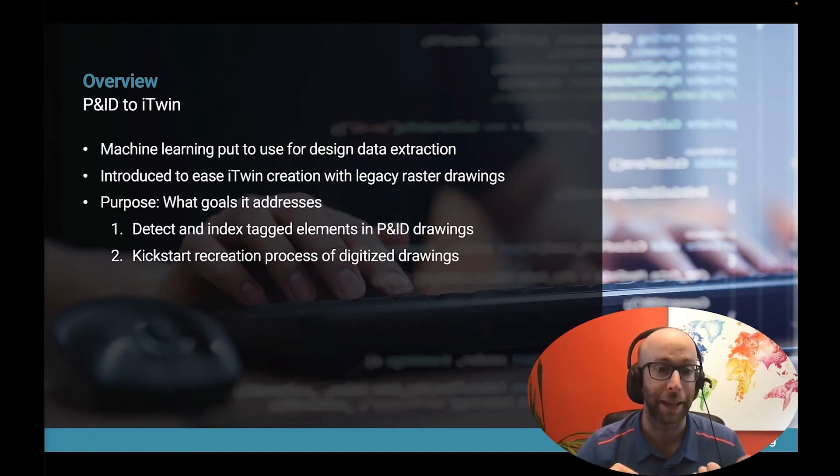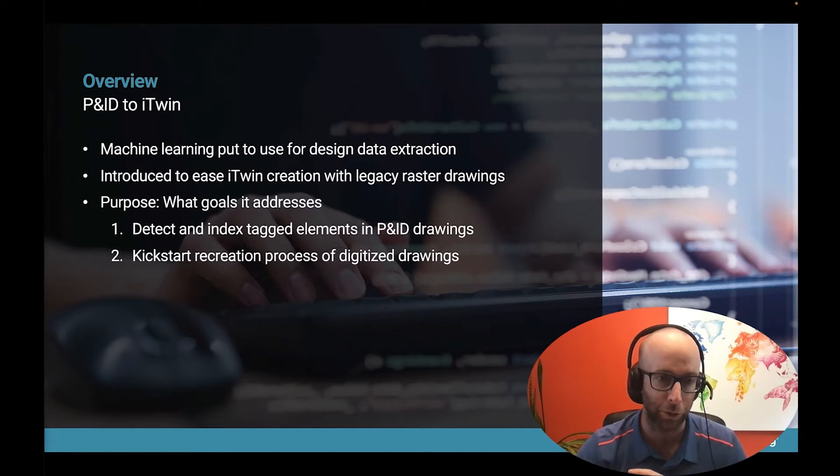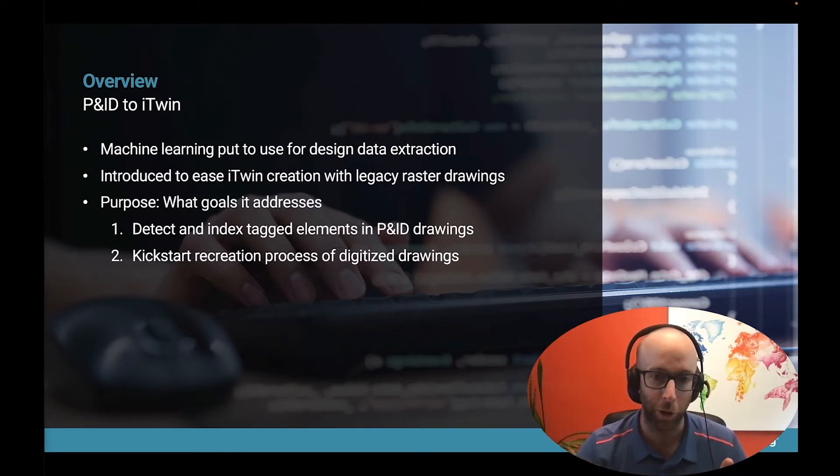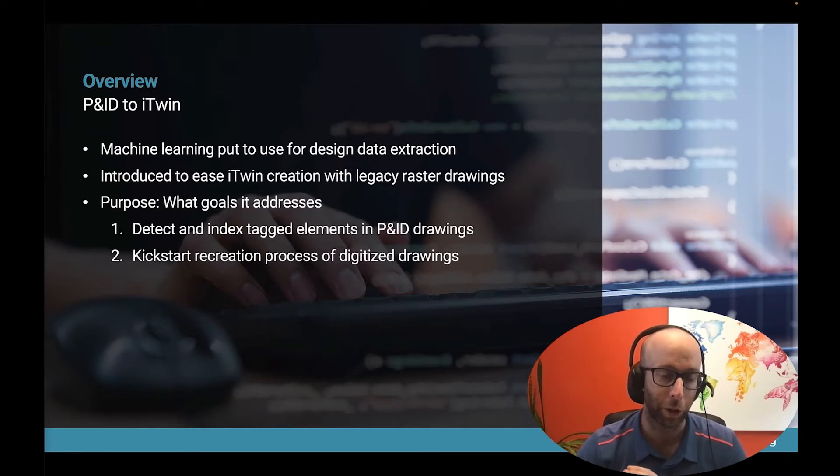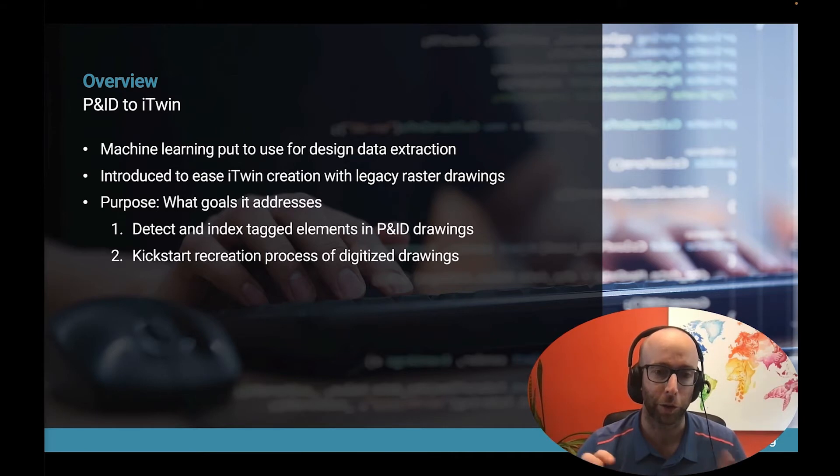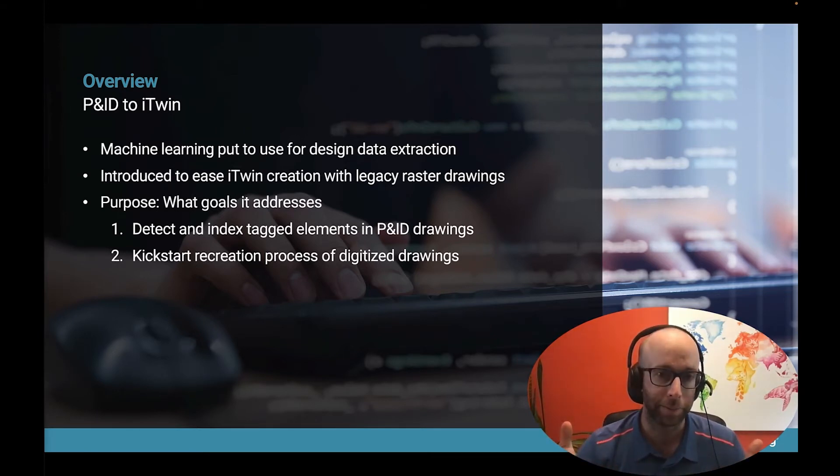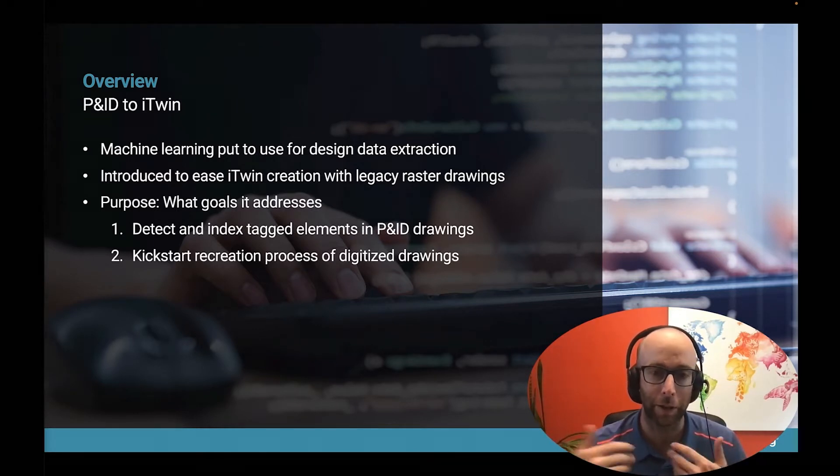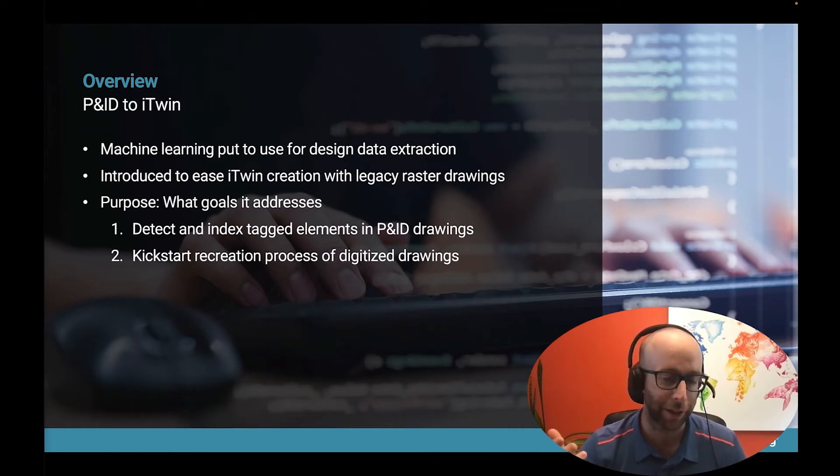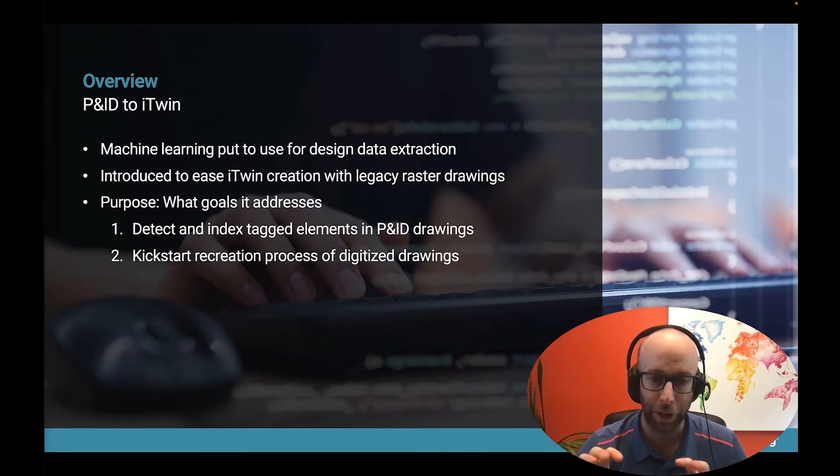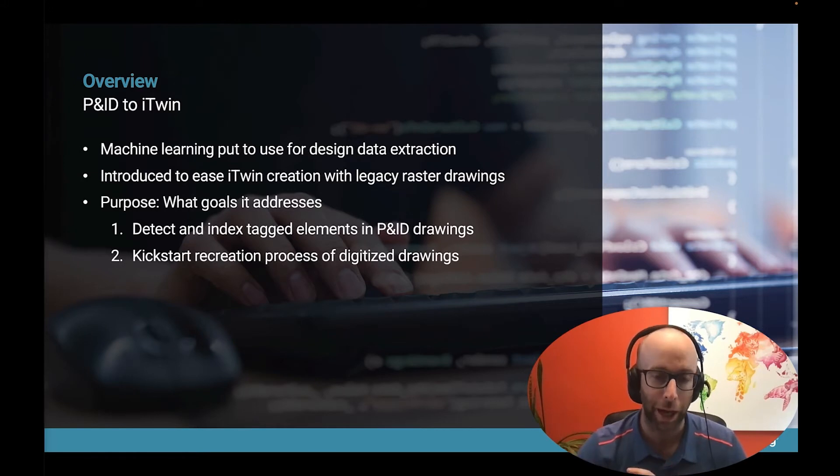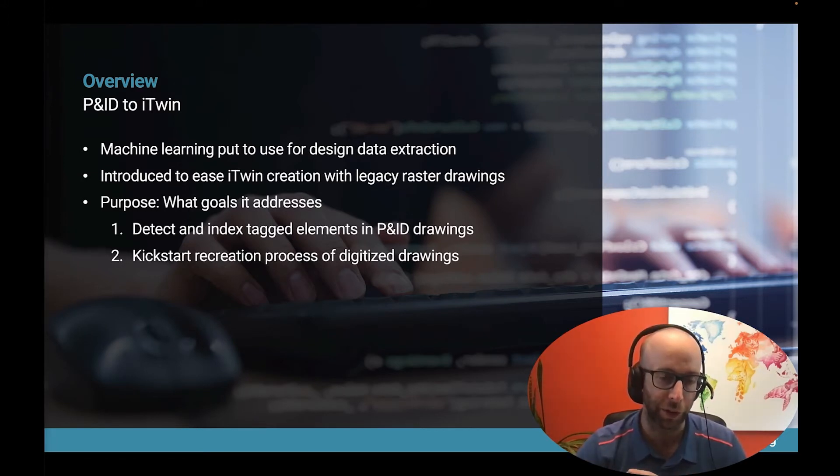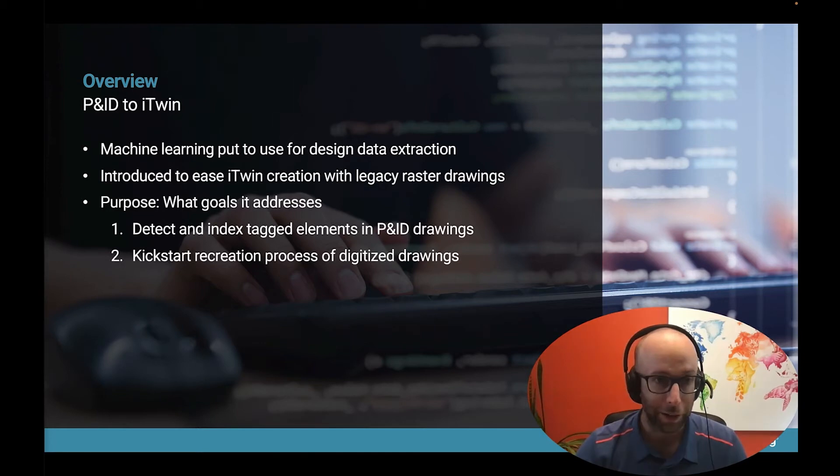The solution can detect equipment on the drawing. It can also detect unique tags for these equipment and associate the tags with the right equipment, allowing you to create a registry of all your tagged elements on your drawing. If you're willing to put a bit more effort and review the results that the machine learning process is giving you, this can also be the start of a recreation process. If you're thinking of updating a plant and you have changes to do on a process line, if you only have a scan document, you have to recreate the whole drawing. But with machine learning, you can start from everything that the algorithm has been able to extract, and then you simply add a couple of changes and review what the machine learning process has given you, because it's not going to be 100% accurate.